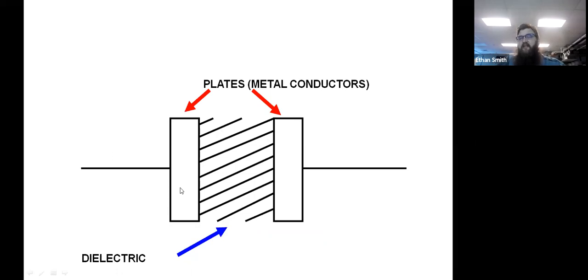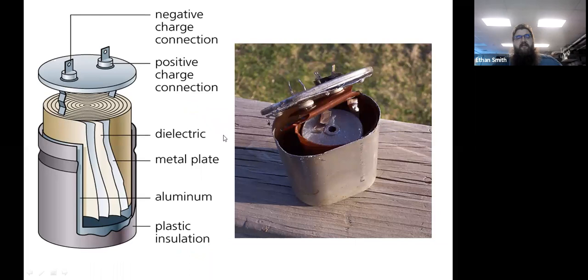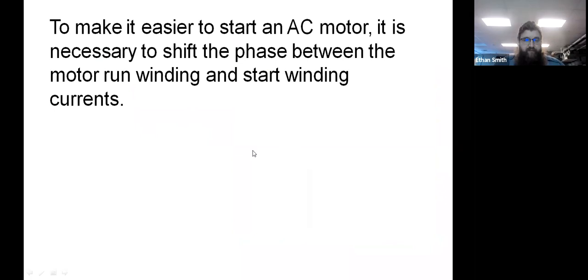Now remember, a capacitor is meant to take an electrical signal and delay it essentially to that start winding. So that start winding then becomes out of phase with the rest of the motor and either helps the motor start or helps the motor run consistently. Okay, and so you have to have your capacitor sized properly so that you get the right amount of out of phase delay. Okay, so there's another picture of a capacitor. That's a naughty capacitor to open up. That's a PCB one. I did not do that. So that's what the capacitor is doing, it's causing that phase shift.